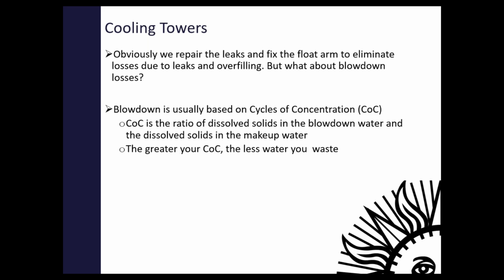Leaks, we can go through and we should seal all leaks. And then overflow we can deal with by fixing the float arm, making sure that float arm shuts the makeup water valve that's coming into the tower when the water level rises high enough in the tower. Those 2 things are simple solutions. Blowdown, however, it's a bit more complex.